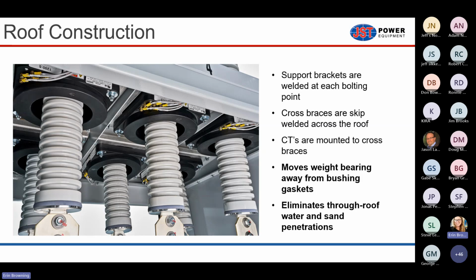I'm going to highlight some of those things now, starting with the roof. So we're on the roof of the breaker, where we have bushings mounted that go through the roof from the top outside to the inside, and then we have CTs mounted per bushing, sometimes up to 2 CTs per bushing. That's a lot of weight to put on the roof. And with that much weight, you're bound to have a lot of flexing going on, a lot of forces, especially every time the breaker operates or every time overhead cables are moving in the wind. Just a lot of forces going on the roof of the breaker.